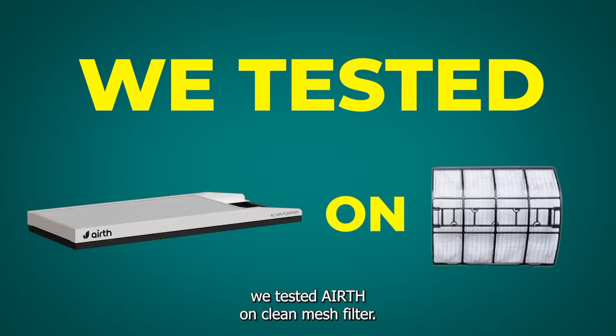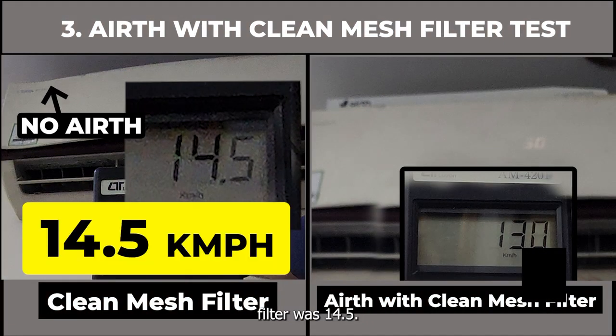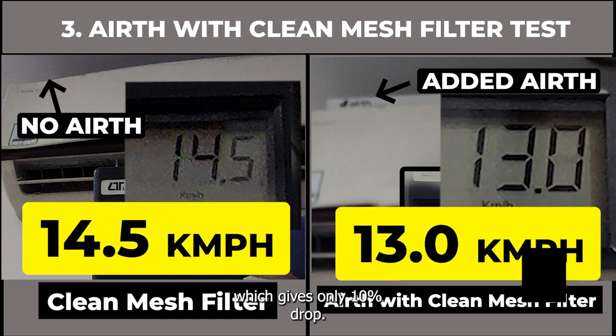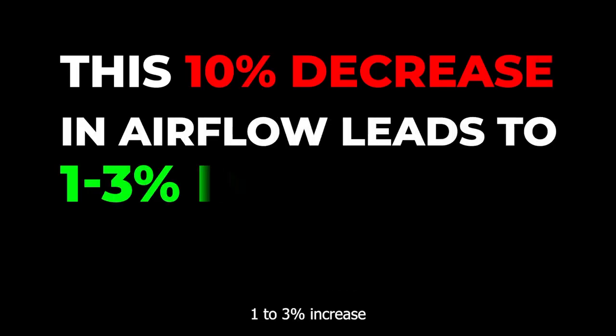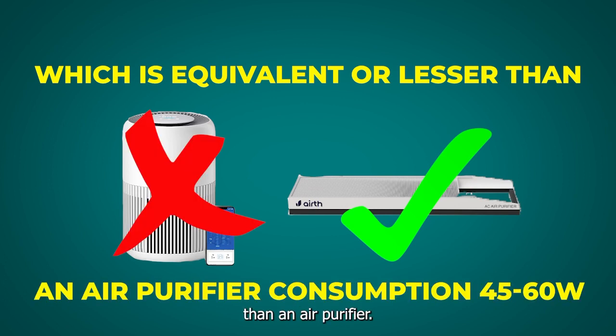As our third experiment, we tested Airth on a clean mesh filter. The airflow with a clean mesh filter was 14.5; when you put Airth, the airflow was 13, which gives only a 10% drop. This 10% decrease in airflow leads to a 1 to 3% increase in electricity consumption of your AC — that is 15 to 50 watts.